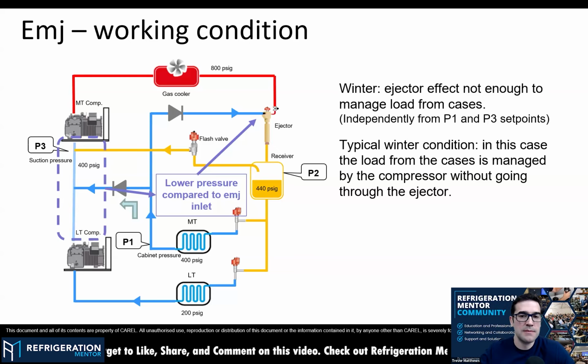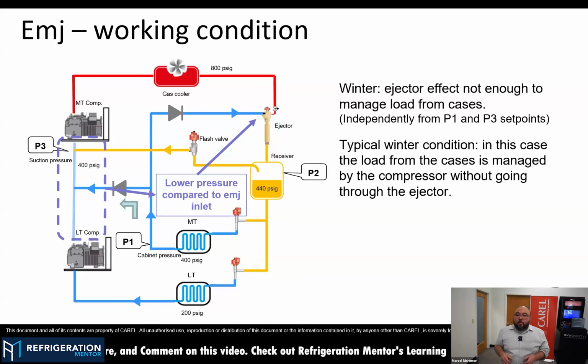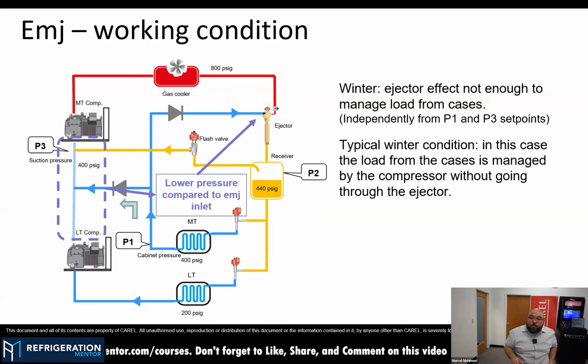No, that totally makes sense. Yeah, we foresee all the conditions, and we have tested this in Northern Europe as well. Even though ejectors do not have the best effect in cold ambient, there are some customers that standardize on ejectors because it's simple for them to have one model of system and only one design of unit. So they can install ejectors everywhere. Since the ejector can be adapted to different conditions, you don't need to worry about whether it's winter or cold. When it's warm and sunny, you get the effect. When it's not, it operates as a traditional rack. So no big deal, even for the high delta temperatures we have here in the US, with summers that are really hot and winters with freezing temperatures. No problem at all.